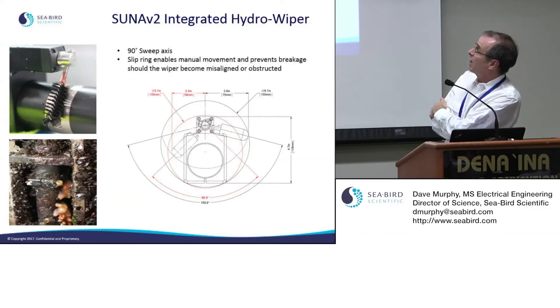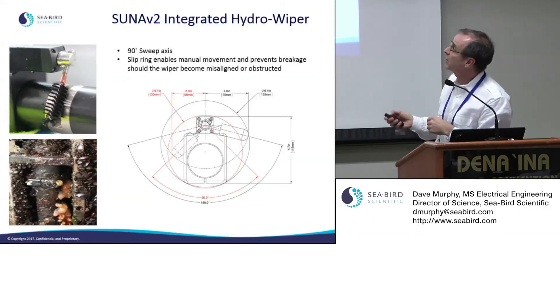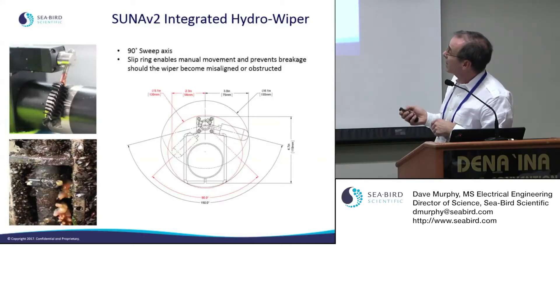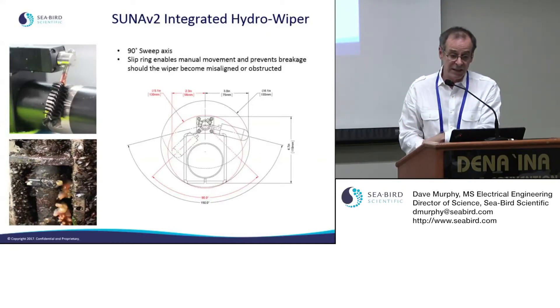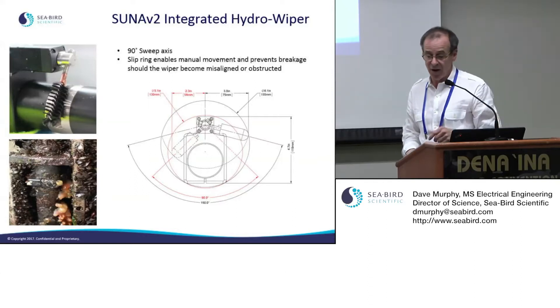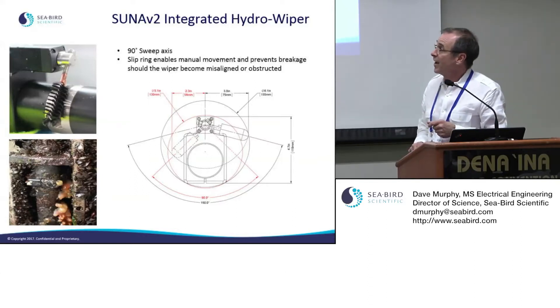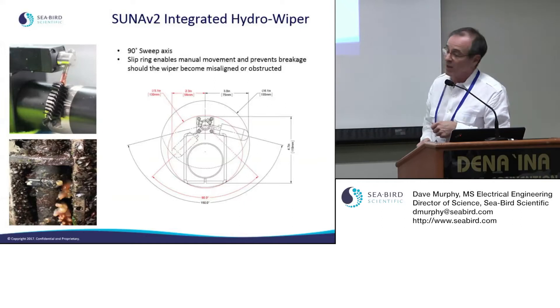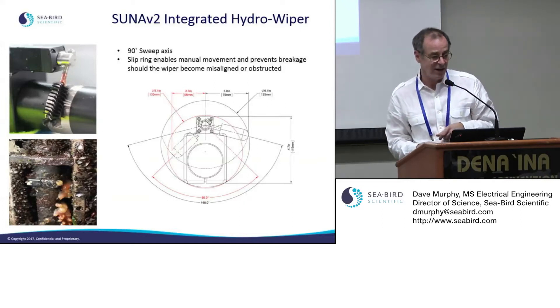The wiper is a bristly brush on a copper stem that sweeps the entire length of the path back and forth. You can set it up to wipe or not, depending on what you want. Every time you take a sample, the hydro-wiper sweeps through and cleans off any accumulation of material in the path.